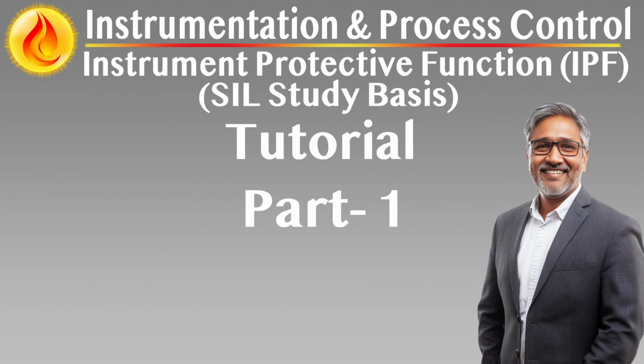Dangerous detected, DD: failures that could impair the safety function but are discovered through diagnostics. Example, relay coil open circuit detected by online monitoring. Dangerous undetected, DU: failures that prevent the IPF from acting on demand and remain hidden until tested or demanded. Example, valve stuck closed despite a correct signal to open, undetected until a trip occurs. Dangerous undetected, DU, failures are the most critical, as they directly influence the calculated PFDavg and define the reliability of the IPF under demand conditions.